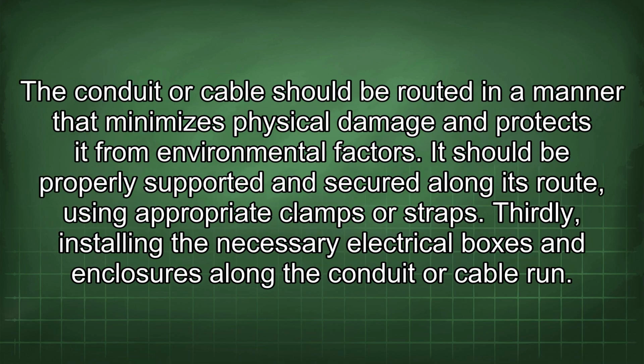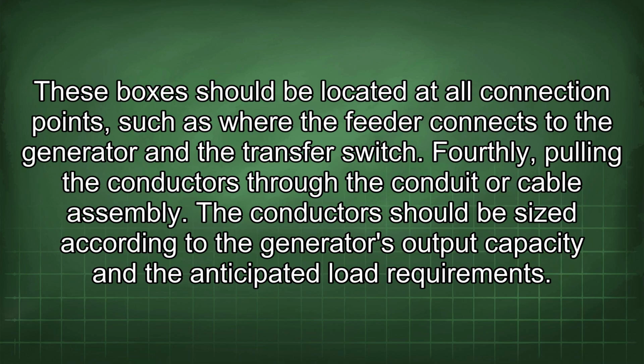The conduit or cable should be routed in a manner that minimizes physical damage and protects it from environmental factors. It should be properly supported and secured along its route, using appropriate clamps or straps. Thirdly, installing the necessary electrical boxes and enclosures along the conduit or cable run. These boxes should be located at all connection points, such as where the feeder connects to the generator and the transfer switch. Fourthly, pulling the conductors through the conduit or cable assembly.